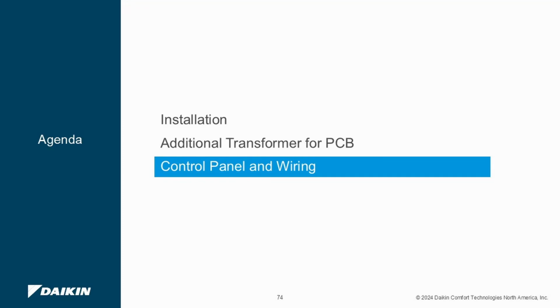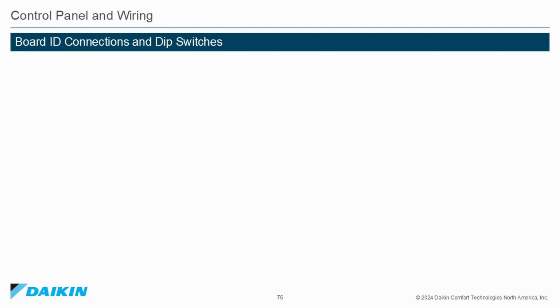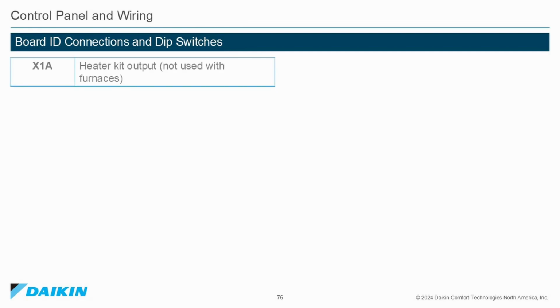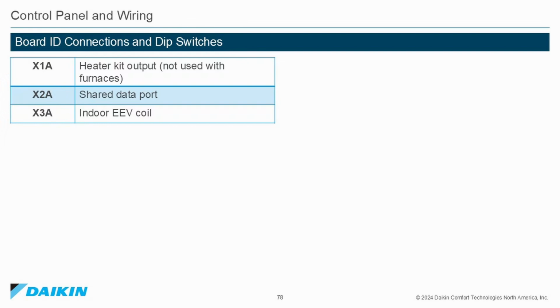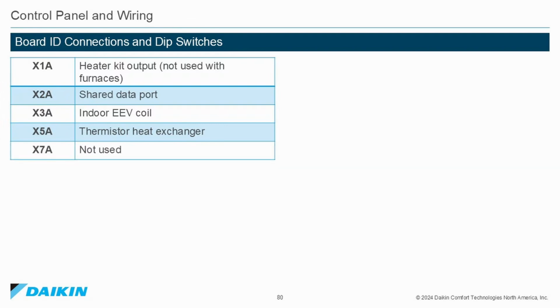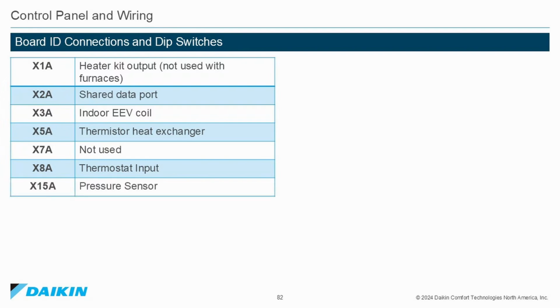Control panel and wiring. Board ID connections and dip switches. X1A, the heater kit output. It's not used with gas furnaces. X2A, shared data port. X3A, indoor EEV coil. X5A, thermistor for the heat exchanger. X7A is not used. X8A, thermostat input. X15A, pressure sensor.